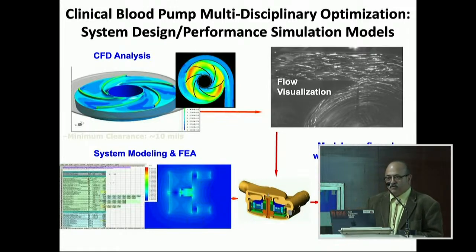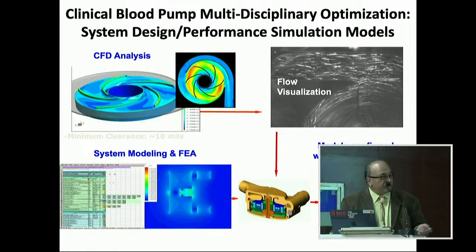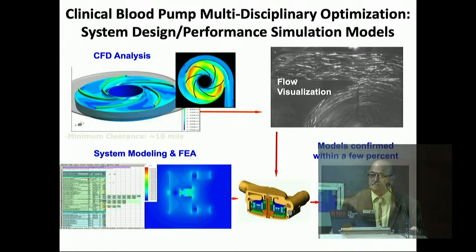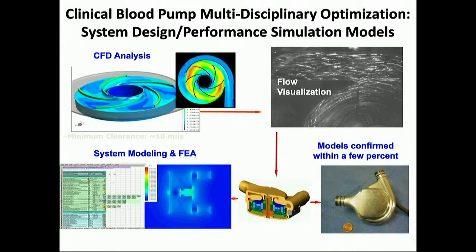So of course, we talked about, Dr. Pillari, you talked about finite element analysis. We did a lot of that, both for computational fluid dynamics, how does the blood behave, and we want to make sure the shear stresses are low enough, and the transit time is low enough that we are not shearing blood cells, because we can pump red liquid, but if we are shearing the red blood cells, there's no point in it. So we have to design it so that the blood cells are happy, or not as stressed, let me put it that way, as it goes through our pump. Then, of course, we did flow visualization. We seeded with red blood cell-size particles. We shone a laser on it, and we just had a transparent model built.